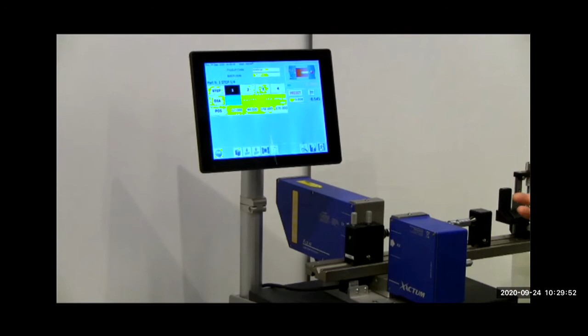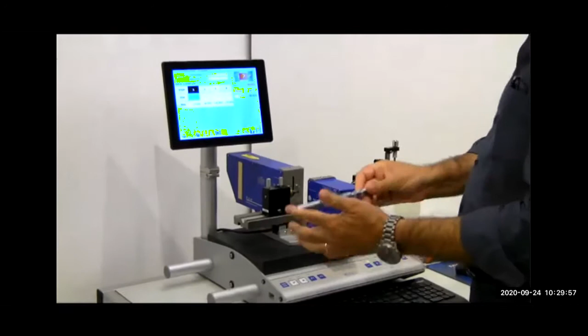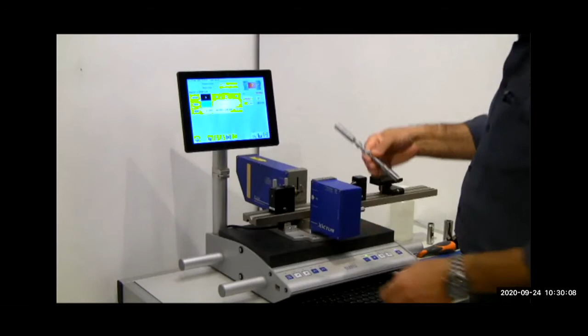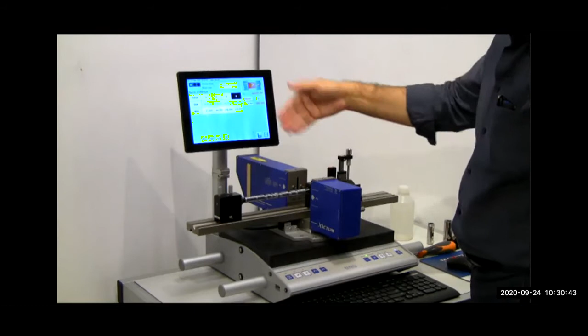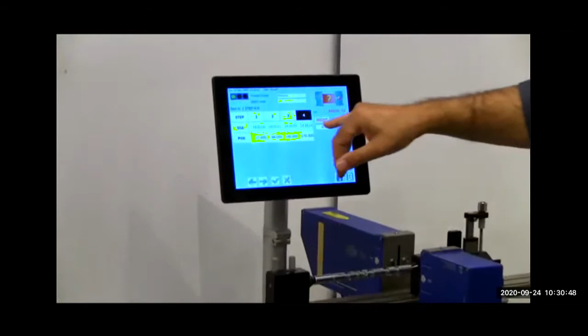In this case, I prepared a measurement routine to make the measurement on the fly of this hydraulic spool. You know that this type of object requires a very tight tolerance, in the order of some microns. We have a lot of customers all over the world that use our system to make the offline check of this hydraulic spool. In this case, I put the spool in one of our supports, this couple of dead centers. And I programmed 4 sections in the spool. In this way, simply passing the object through the measurement field, I have the measurement of the 4 sections. They are all green, and the traffic light is green, so the piece is okay.